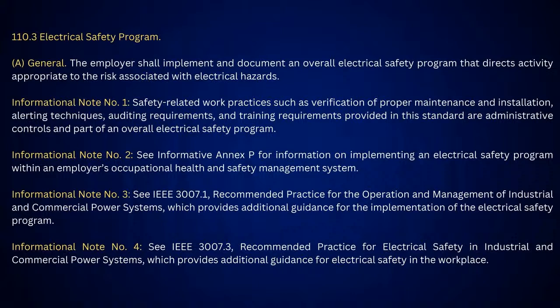Okay. Now, informational note number 1 says safety-related work practices such as verification of proper maintenance and installation. I want to stop right there, because when I look at the National Electrical Code, that's your design and installation manual. Once you've met that, as far as the 70E committee is concerned, the equipment is in proper operating condition, in other words, normal operating conditions. It's not abnormal. But it can become abnormal if you haven't provided proper maintenance on that equipment.